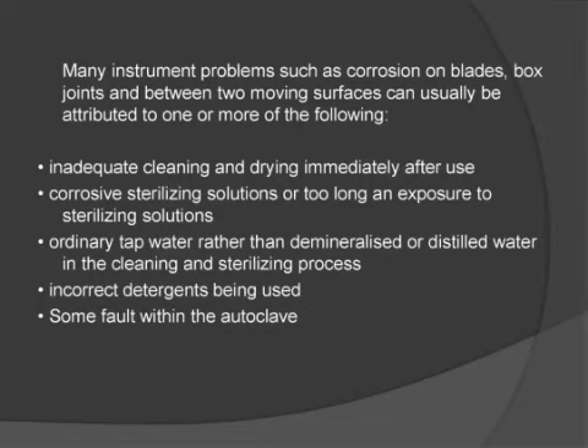You must use purified and sterilized water, or distilled water, for the sterilizing process of surgical instruments. And do not use local brands of detergent solutions for the sterilizing process. And the autoclave is very important. Sometimes the autoclave will be faulty, and then this will happen.